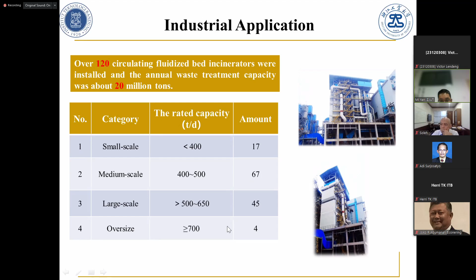This is a case of a CFB. The steam evaporation rate is 45 tons per hour, temperature is 485, and the steam pressure is 5.3. Feed water is 150. And the design waste heating value is lower because it is an old one. The capacity is 800 tons per day. The heat efficiency is 78, and the primary air ratio is 40%. As mentioned, there is 50 to 55 primary air, right? And the primary and secondary air is 380 or 350, much higher than the grate.